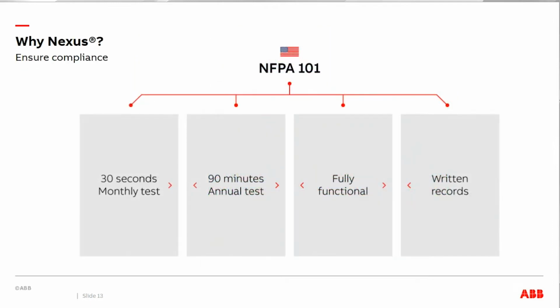Nexus Pro allows the end user to schedule testing for the appropriate duration and intervals automatically or at any time. The system not only tests the devices, it will also notify the user of any units requiring replacement parts by catalog number. The system also records all history of tests performed, to be accessed at any time.